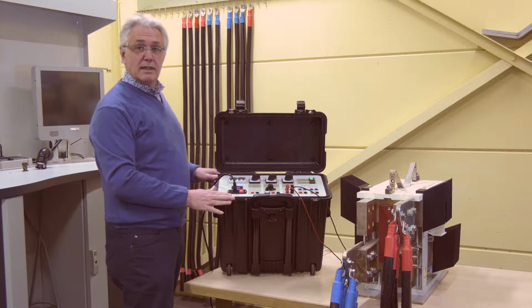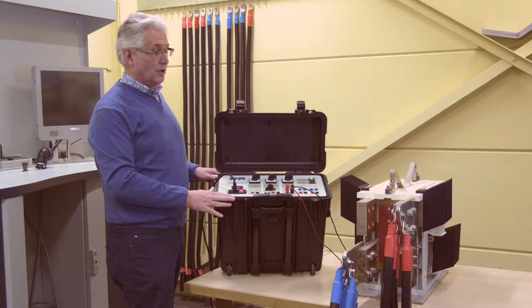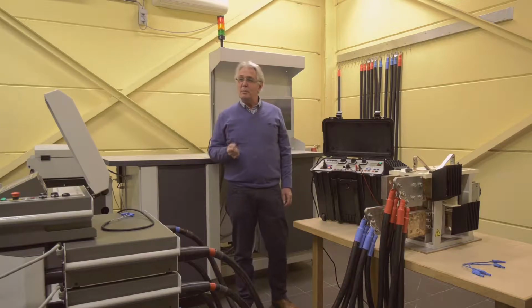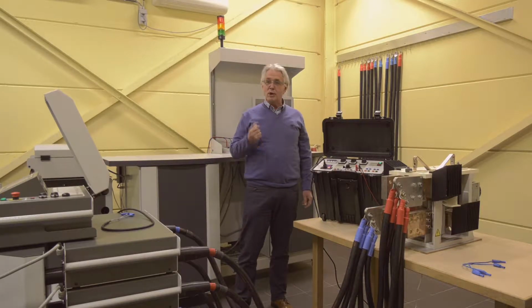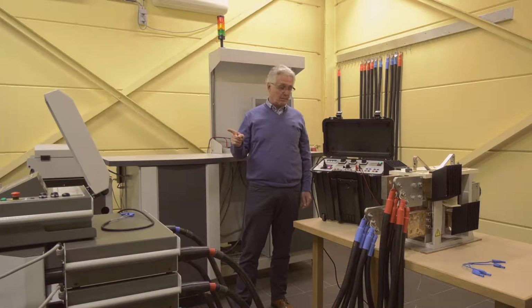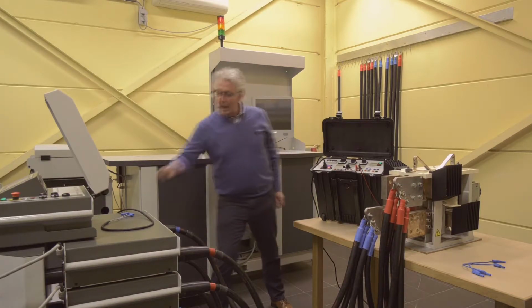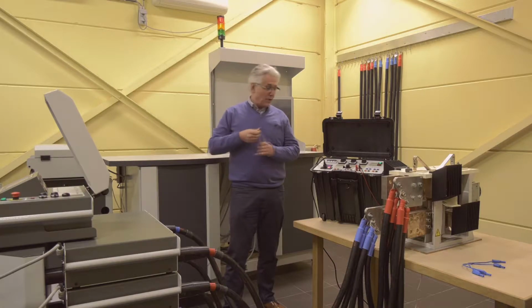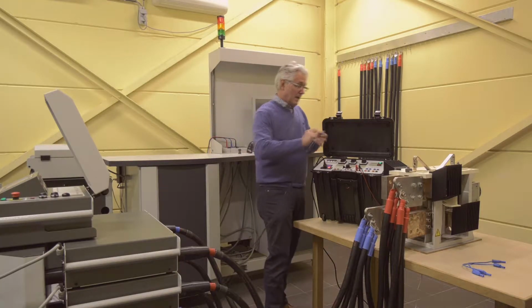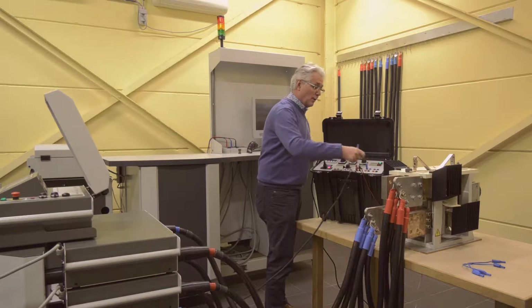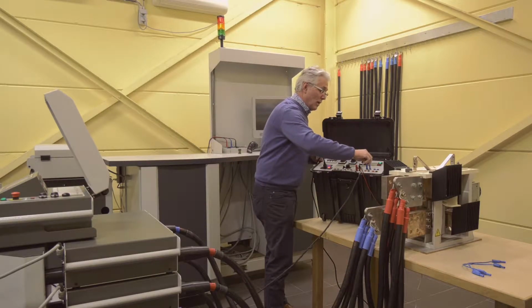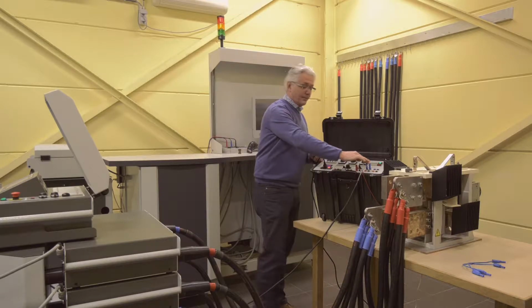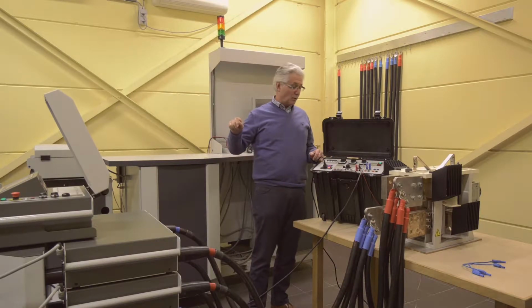So the BCD is the ideal device to open and close breakers in a railway environment. Another thing we can do with the BCD is measure the manual closing time and the manual opening time of the circuit breaker. In order to do that, we need also the Balto system. What I'm going to do now, I'm going to connect the BCD to the Balto system. And what we do here, we connect this dry contact to the trip input of the Balto controller.